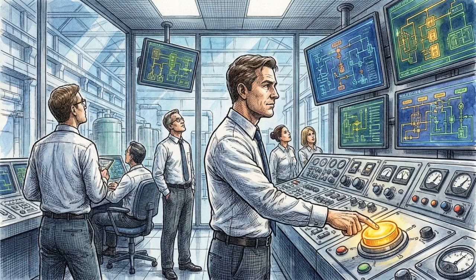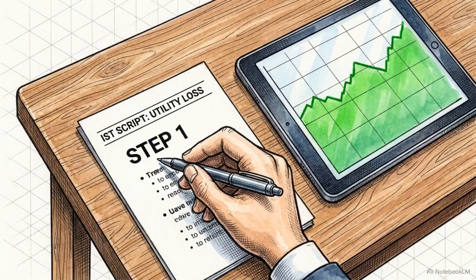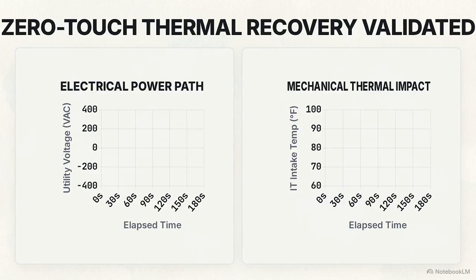The Integrated Systems Test, or IST, introduces controlled disturbances to prove the infrastructure survives cross-discipline failures. Every IST script follows a 7-step format, beginning with a pre-brief to establish safety protocols and a stable baseline for all system trends. The trigger simulates a utility loss. During the observe step, human intervention is forbidden. Automated systems must independently detect failure, transfer load, and re-engage cooling. Systems hold this failure state to measure thermal impact before the restore phase returns the facility to normal.